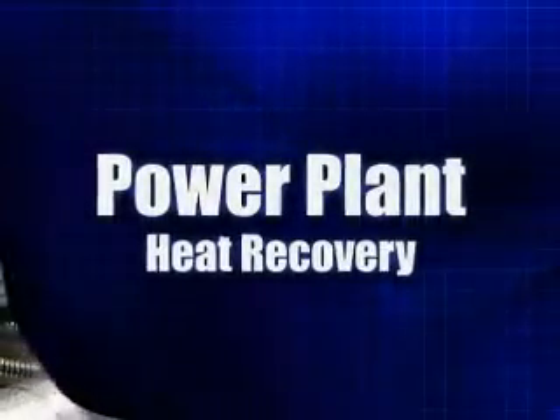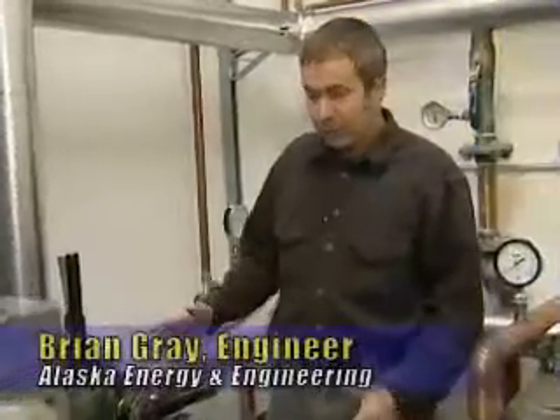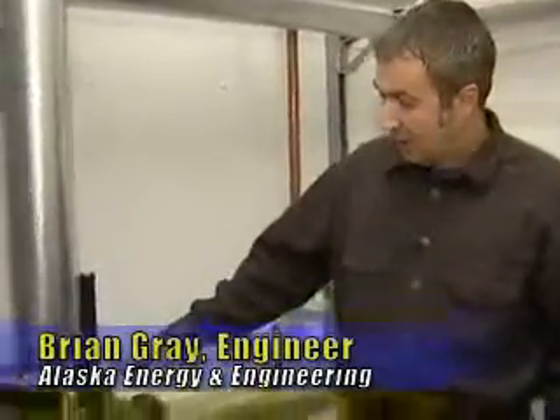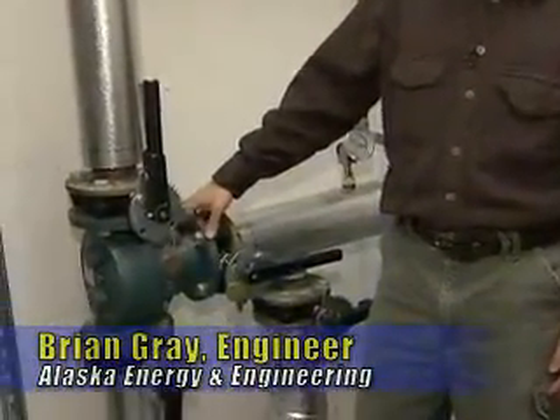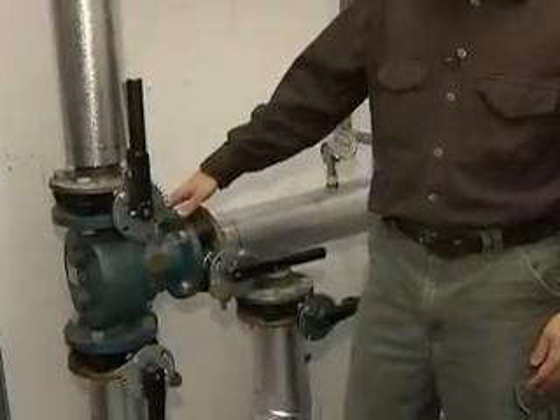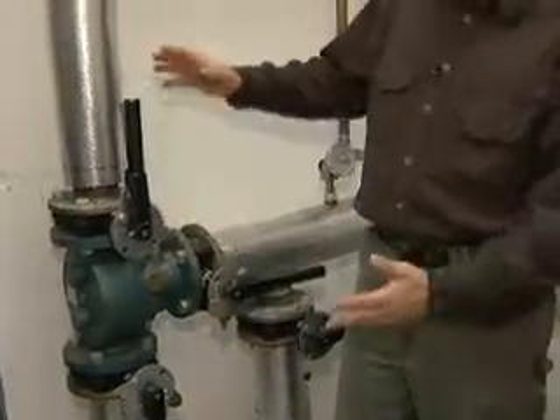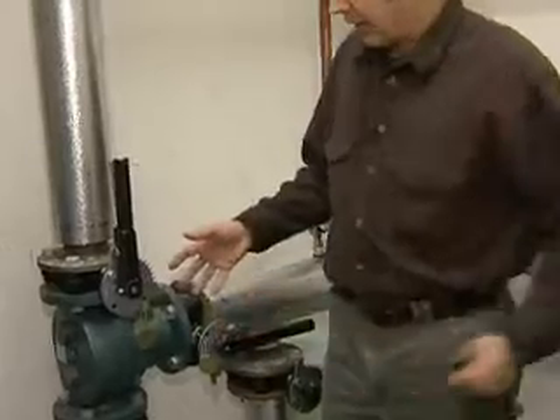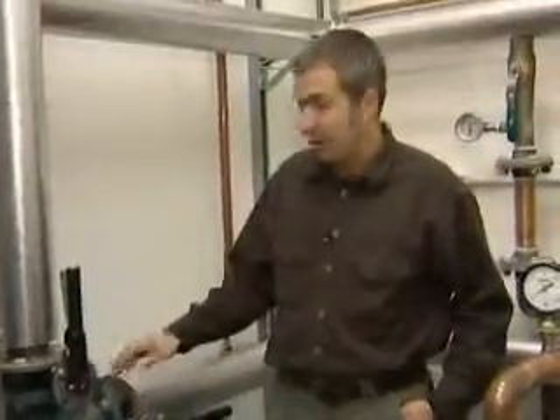Okay, this power plant is equipped with a heat recovery system. We're going to go through some of the components of this. This is a three-way thermostatic valve. It's often called an AMOT valve.